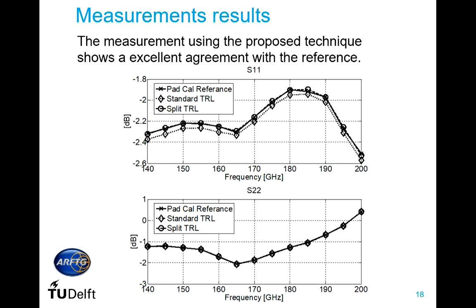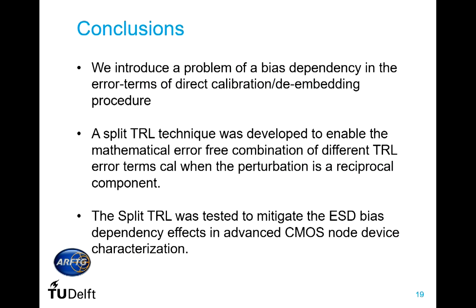This measurement should exactly match what we get directly at the pads using the TRL calibration at the pads, and in fact that is what we see in the results. Here we see S11 and S22 of our open measured at the pads. Using the split TRL we get excellent agreement with the reference measurement. We clearly see an error when using a standard TRL made with zero volts at both ports. Note that S22 does not change between methods because we always applied zero voltage at port two.